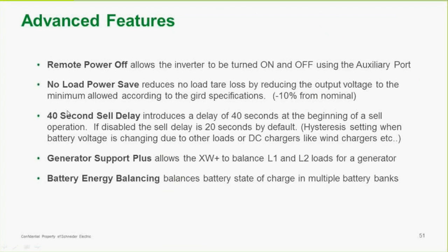And there are a few advanced features. Remote power off is available to turn the inverter on and off using the aux port. There's a no load power save, so if you have absolutely no load on the inverter, this will bring the power consumption way down, even lower than the tare load setting. There's also a 40-second Sell delay option. When the inverter is going in and out of Sell mode, you can set the delay to 40 seconds instead of the 20-second default.